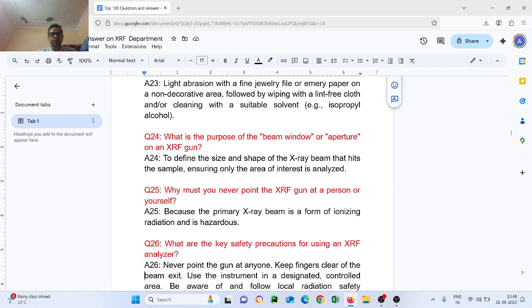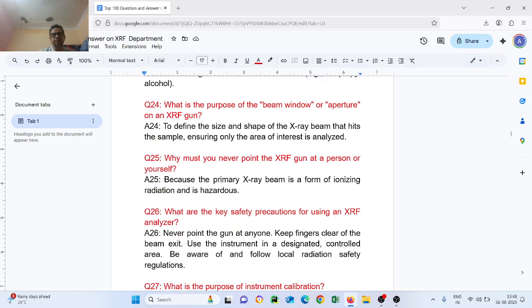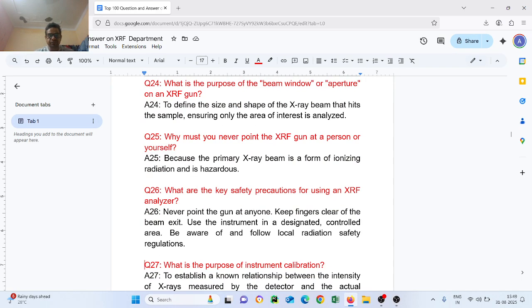Question number 26. What are the key safety precautions for using an XRF analyzer? Never point the gun at anyone. Keep fingers clear of the beam exit. Use the instrument in a designated control area. Be aware of any local radiation safety regulations.